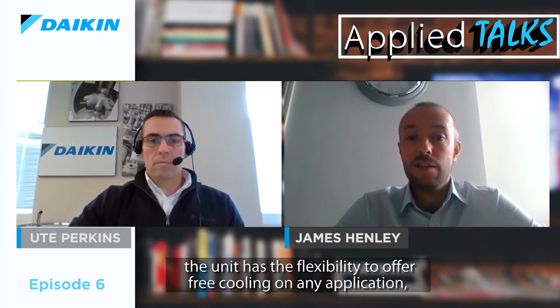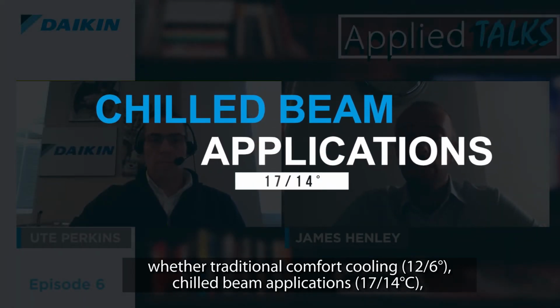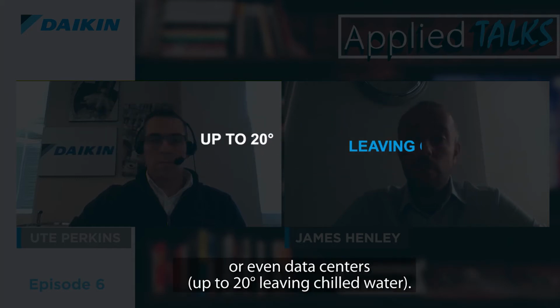And with the two different free cooling levels, the light version starting free cooling from 4 degrees below your chilled water set point and giving up to 25% free cooling, or the full version starting from just 1 degree below your chilled water set point and up to 80% free cooling capacity. The unit has the flexibility to offer free cooling on any application, whether that's traditional comfort cooling at 12/6, chilled beam applications at 17/14, or even on data centers up to 20 degrees chilled water leaving temperature.